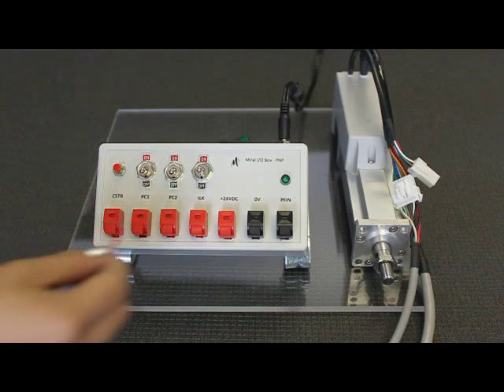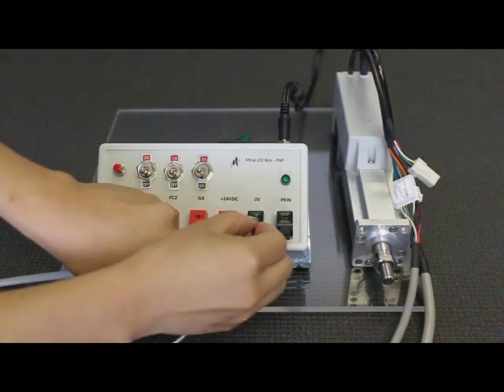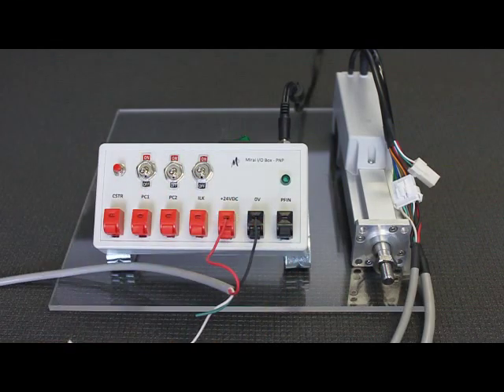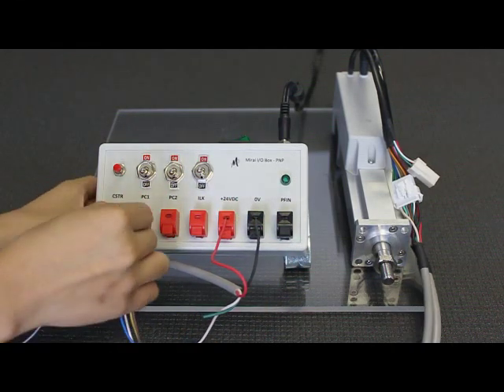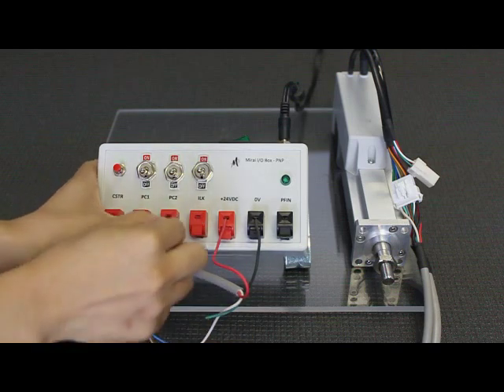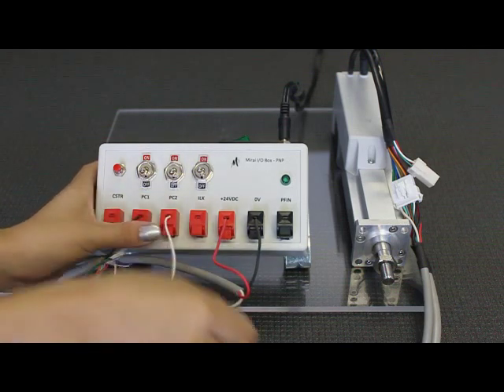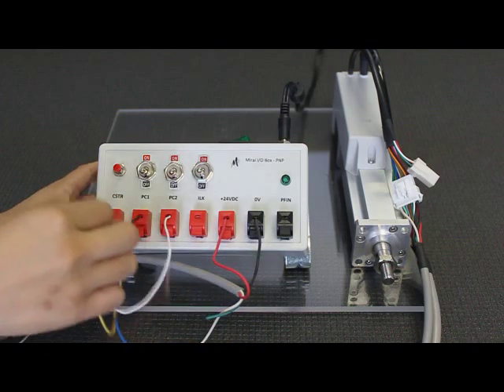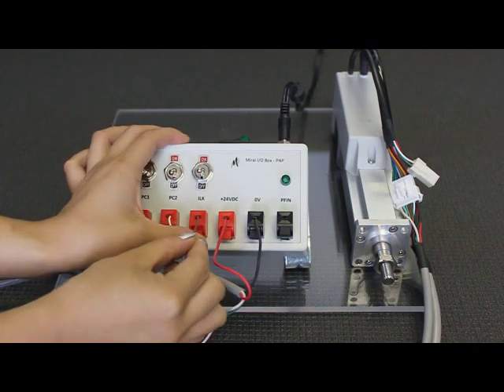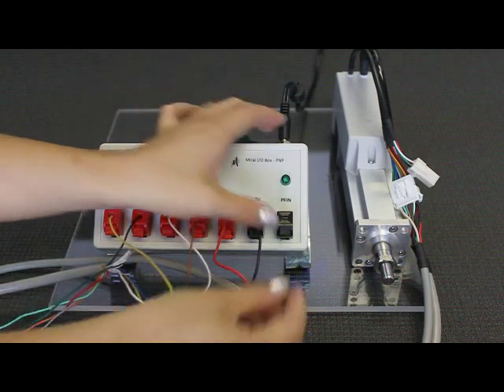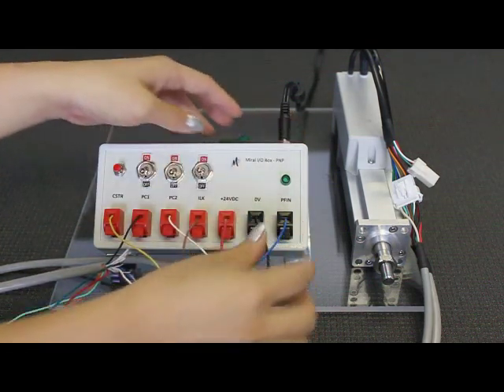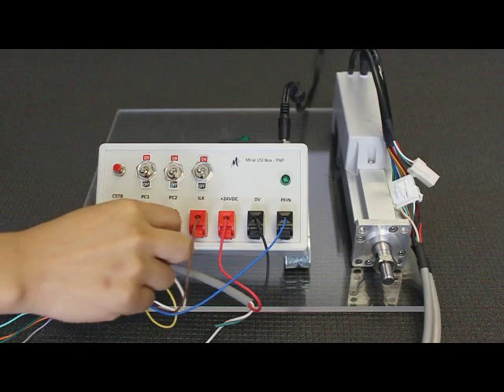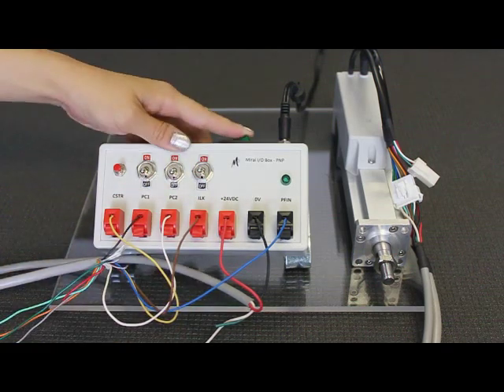First, connect the red and black wires from the power cable to the 24V and 0V. Next, from the I.O. cable, connect the black wire to PC1, the white wire to PC2, the yellow wire to CSTR, the brown wire to ILK, and the blue wire to PFIN. The inputs and outputs can be damaged by wiring errors, so check your wiring carefully and go ahead to apply 24V power.